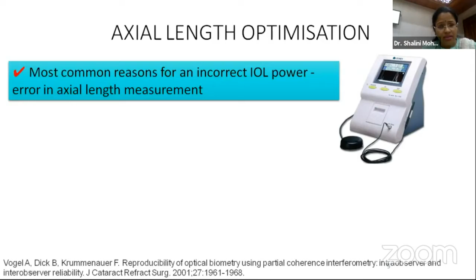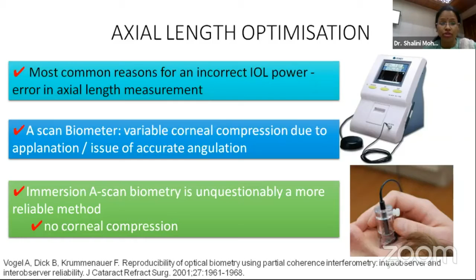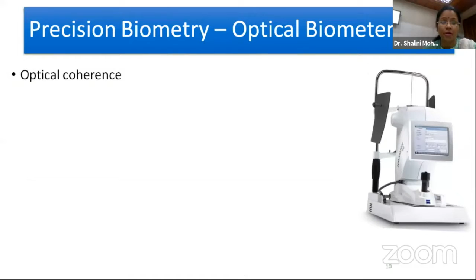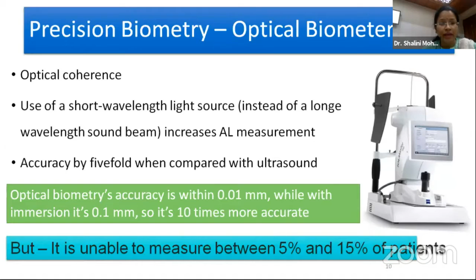So if we see that ultrasonic A scan biometers, due to variable corneal compression and because of the issue of accurate angulation, are not very reliable. So immersion A scan biometry is unquestionably a more reliable method because of no corneal compression, and when used with Prager shells, that gives very good results. But if we want to have precision in biometry, optical biometer is the answer. It uses a short wavelength light source, as we know, and it increases the accuracy by 5-fold when compared to ultrasound. Moreover, it has been seen that optical biometer accuracy is at the level of 0.01 millimeter in comparison to immersion, which is 0.1. Still, we have so many patients in which optical biometer is not possible, and then immersion is the answer in such patients.